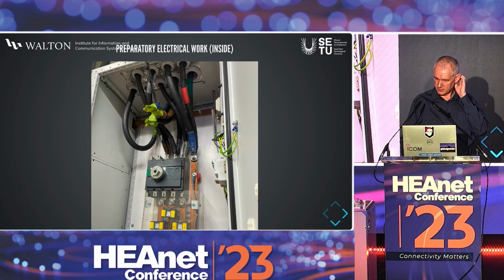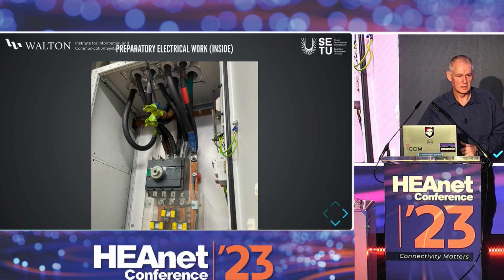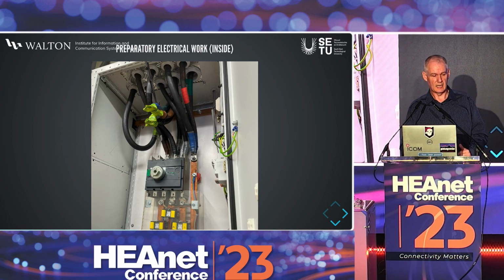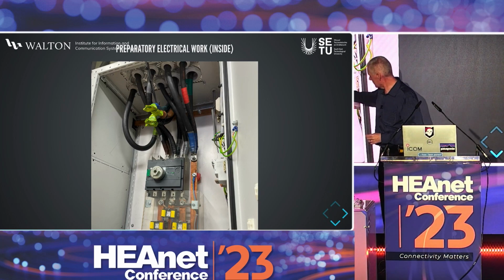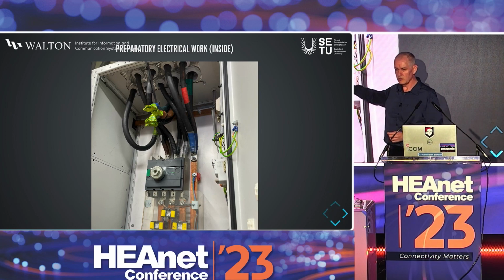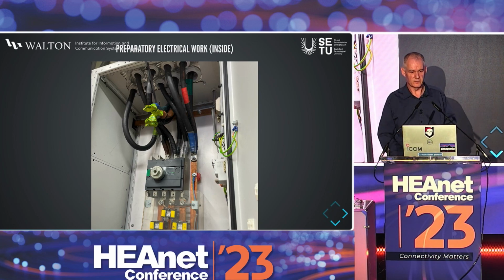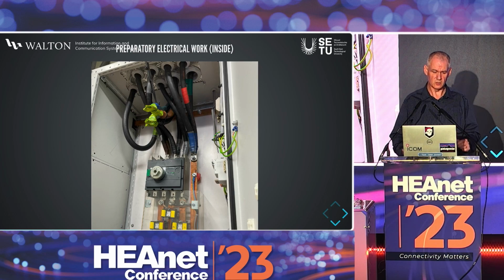Then they started preparatory electrical work - 120 square cables, 2 per leg, and that work had to start. You'll notice the neutral isn't switched, and that's one of the reasons we had to shut the power to the building. Because that's not switched, we couldn't do any work with the building live from a safety point of view. So we were told.